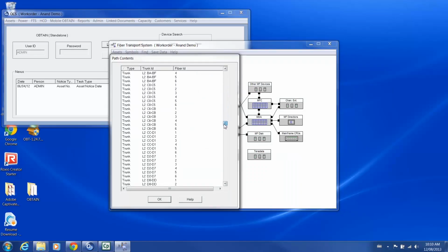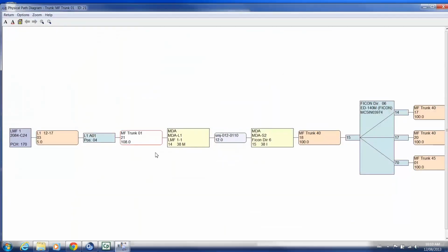It consists of a mixture of patch cables and trunk cables. If we select a single fiber pair from inside the trunk cable, a true DCIM database will dynamically generate a view of the full connectivity and impact of the fiber pair. The generated view shows fiber pair 21 as being part of a 108-foot cable, with connectivity on one side through a mounting bracket and harness cable to port 170 of a server.